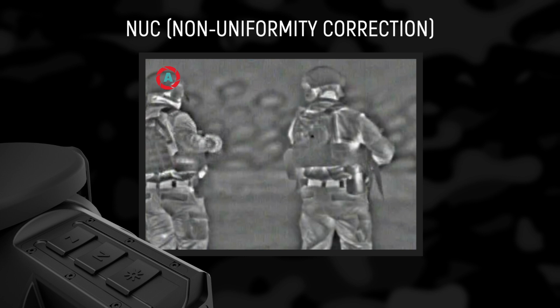The NUC algorithm is activated manually or automatically through specified intervals by pressing the N button. Pressing and holding the button for more than 2 seconds deactivates the AutoNUC function as the icon Automatic NUC disappears. In that case, the NUC will be carried out manually only when pressing N. By pressing the N button again and holding it for more than 2 seconds, it activates the AutoNUC function, and an icon appears on the upper left corner of the screen.